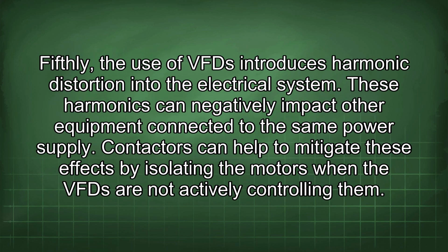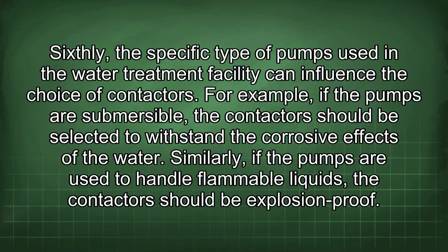Fifthly, the use of VFDs introduces harmonic distortion into the electrical system. These harmonics can negatively impact other equipment connected to the same power supply. Contactors can help to mitigate these effects by isolating the motors when the VFDs are not actively controlling them. Sixthly, the specific type of pumps used in a water treatment facility can influence the choice of contactors. For example, if the pumps are submersible, the contactors should be selected to withstand the corrosive effects of the water. Similarly, if the pumps are used to handle flammable liquids, the contactors should be explosion-proof.